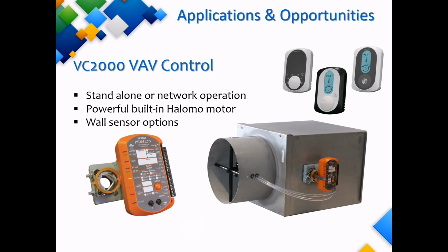This can be particularly useful for a retrofit project, where the customer may not be willing to replace the entire control system on day one, and would rather replace the existing controls one sector at a time as their budget allows. In this case, Prolon's controllers can be installed one at a time and would operate standalone until the day where the customer would want them to be networked, in which case we simply have to connect them together using a 2-conductor cable. Okay, on to the VC2000.